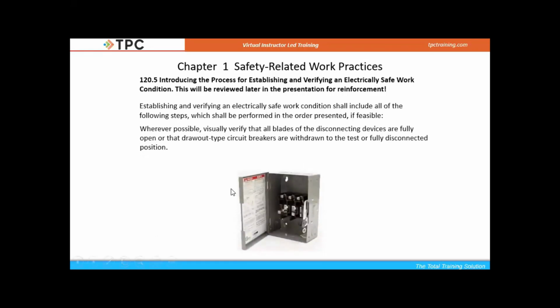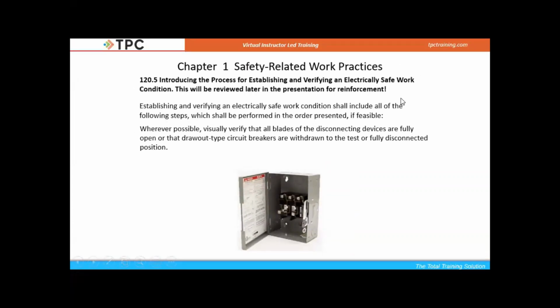I'm going to zoom in on this one a little bit. What we have to do now is take a visual look, and make sure those blades in this disconnect have pulled out of the blade holders. This is a mechanical device, and at times it could fail on us, and we do not want that to happen. So we're going to take a visual look.